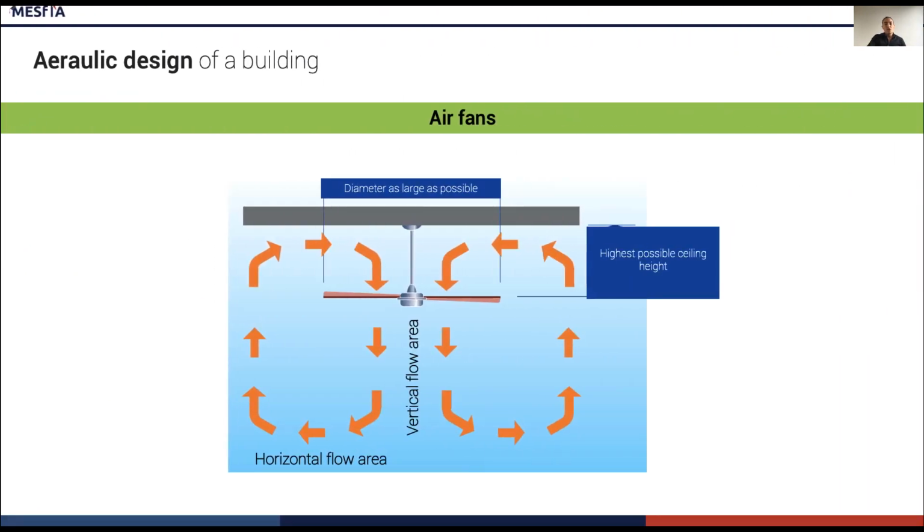If natural ventilation alone is not sufficient, it is necessary to energize the airflows inside to more effectively evacuate heat loads and create a draft on individuals. Fans increase fluid circulation, which results in physiological cooling. They can be used to supplement insufficient natural ventilation. The larger the blade diameter, up to 1.2 meters, the more efficient the fans.